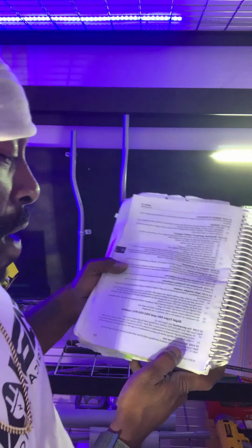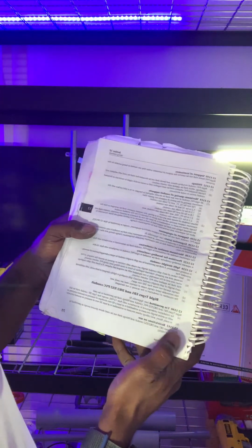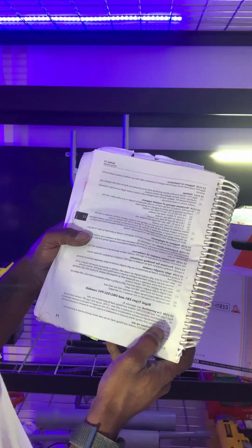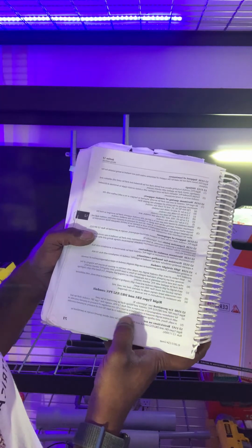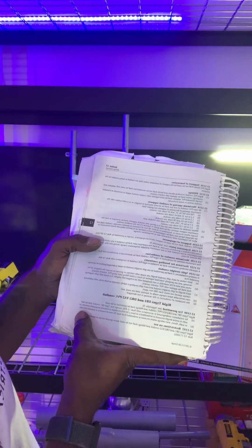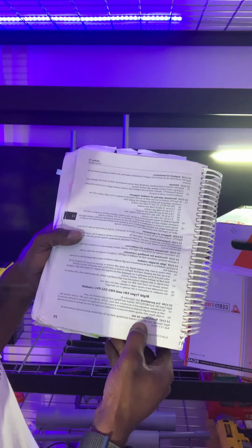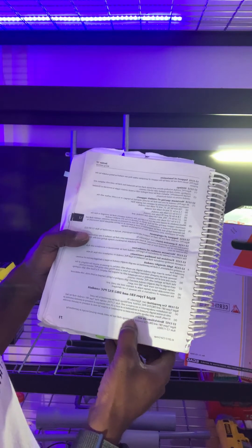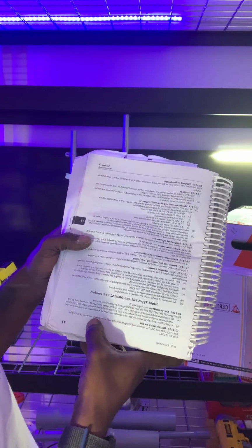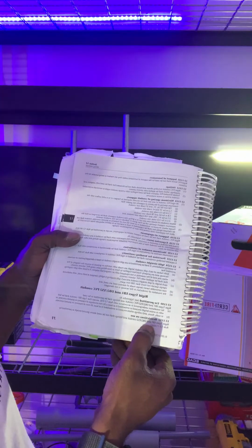12-1150B. So if I go over to that rule, that is referring me back to this rule here. And it says in walls, floors, and ceilings where encased or embedded in at least 50mm of masonry or poured concrete. So rigid type EB1 and DB2/ES2 conduit and fittings shall not be used above ground except as permitted by Rule 12-1150B.